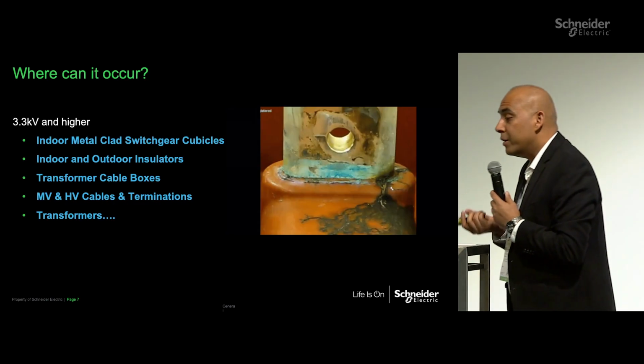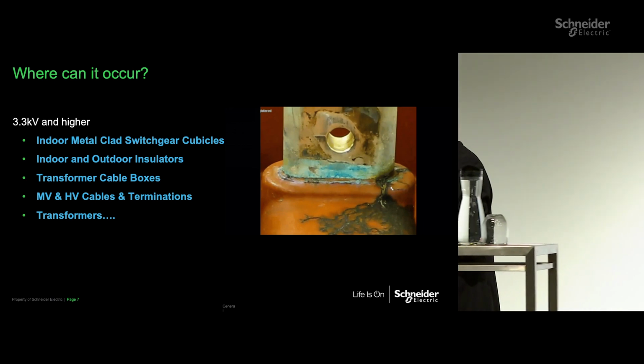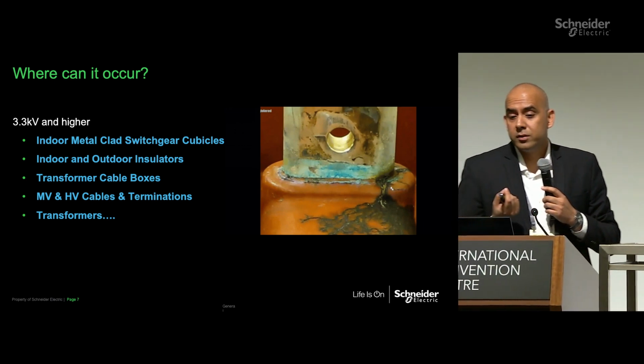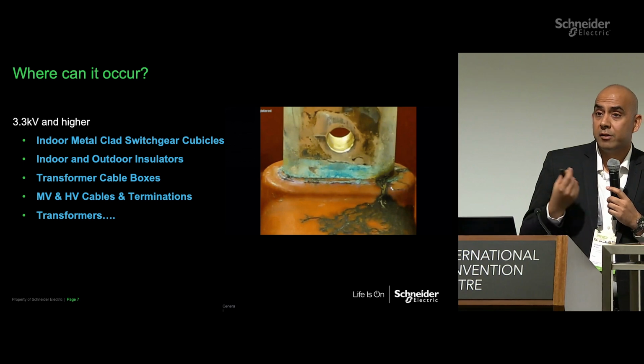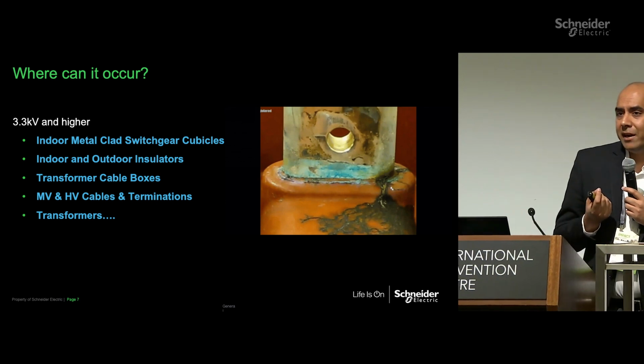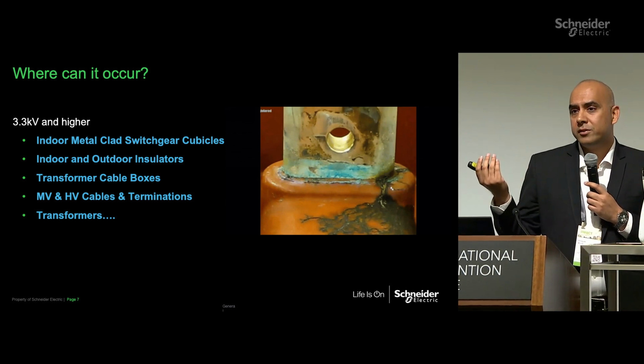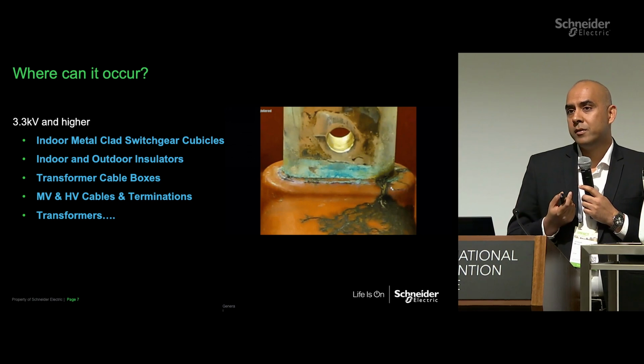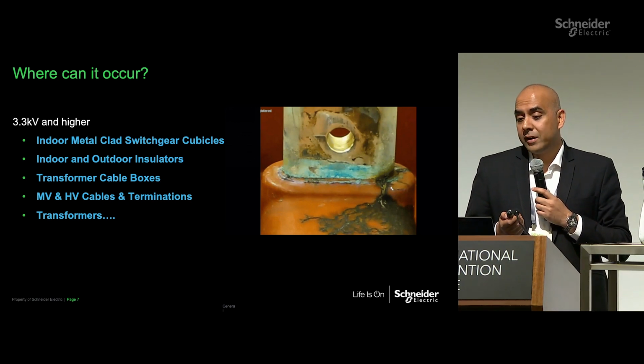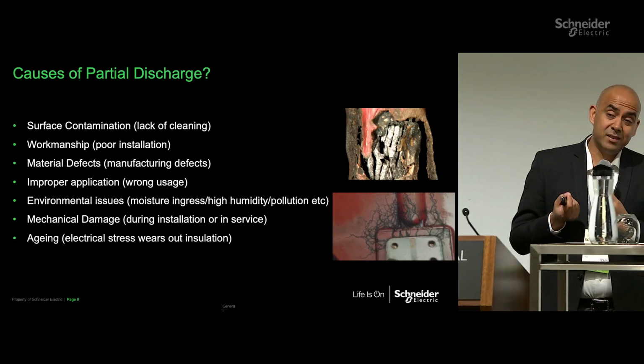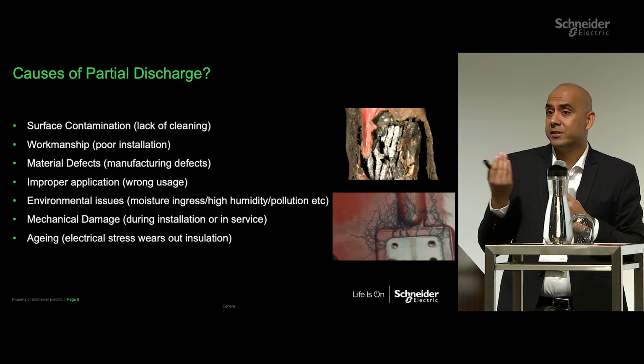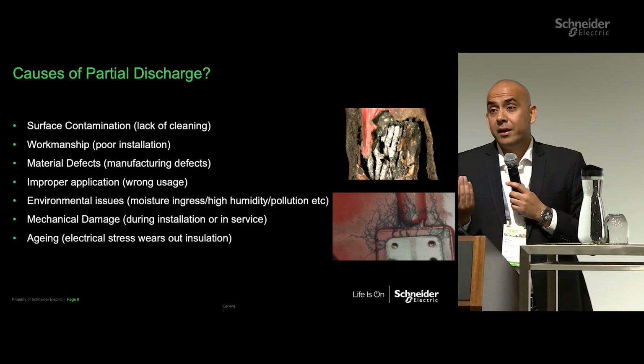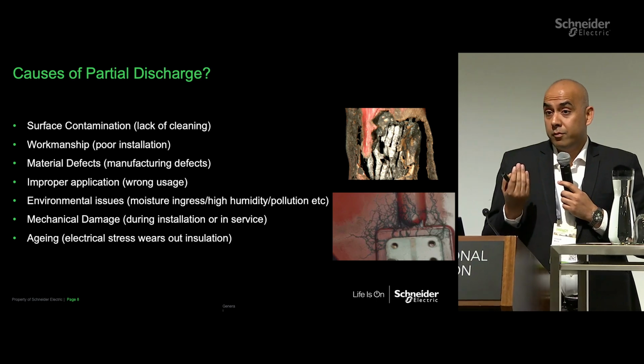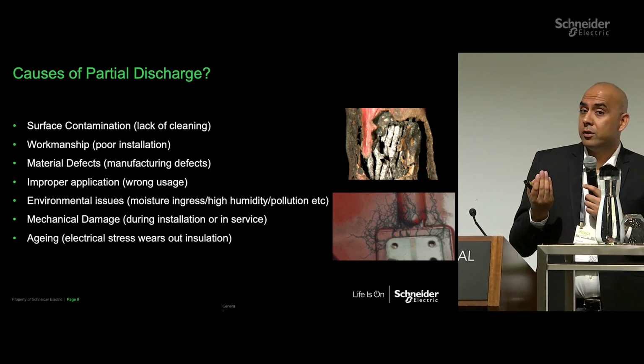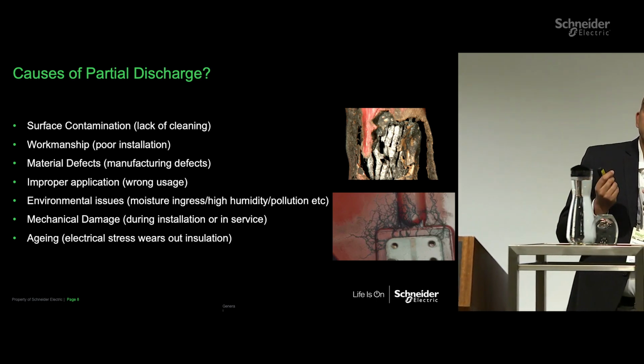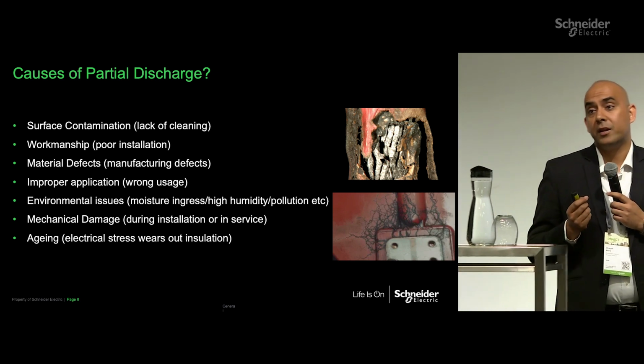So typically, it can happen in indoor switchgears, insulators, cable boxes, cable terminations, transformers. Rather, every electrical equipment in 3.3 kV and above systems has a risk of partial discharge. And what are the reasons why it can come in? Very basic is surface contamination. It could be a dusty environment, no real maintenance, lack of cleaning, workmanship, specifically poor installation. In fact, poor installation is one of the major reasons for partial discharge.